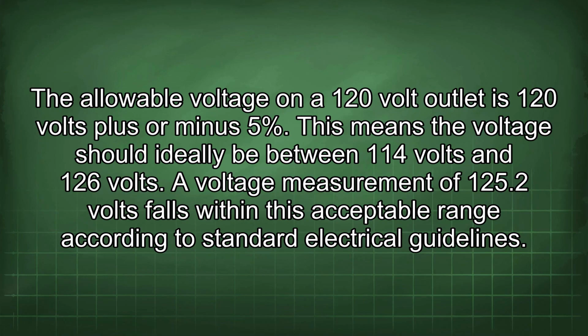The allowable voltage on a 120 volt outlet is 120 volts plus or minus 5%. This means the voltage should ideally be between 114 volts and 126 volts. A voltage measurement of 125.2 volts falls within this acceptable range according to standard electrical guidelines.